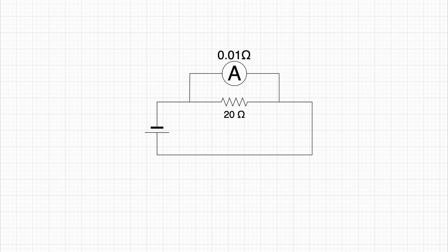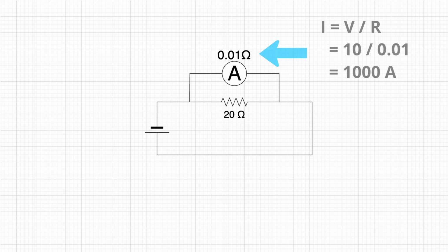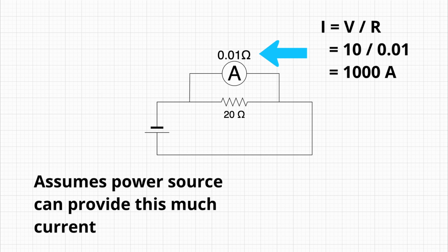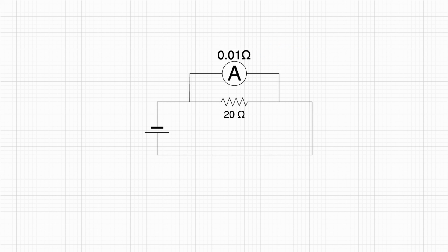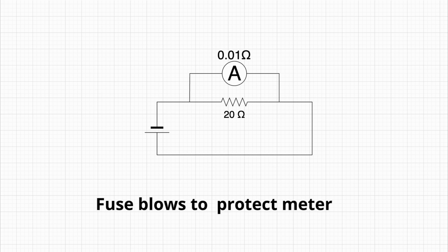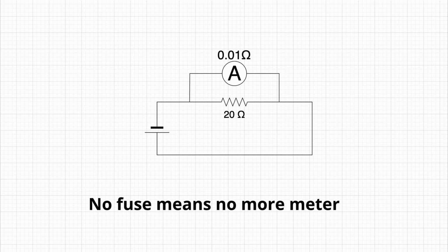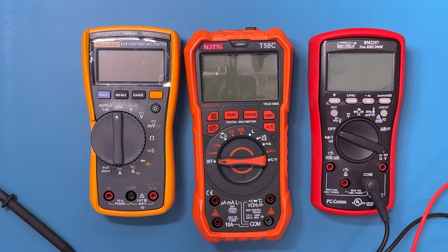Now, when we attempt to measure voltage using the current measurement pathway in the multimeter, we are placing the shunt resistor in parallel to the circuit we are measuring. Because the shunt resistor has a very low resistance, close to that of a pure short circuit, almost all the current that can be provided by the circuit at that point will flow through the shunt. As you know, a short circuit causes the opportunity for a very high amount of current. In a meter with a fuse, the fuse will blow, thereby protecting the internal circuitry of the meter. If no fuse is present, the circuitry will be destroyed. The best choice is to prevent this situation from occurring in the first place. Different meters have taken different approaches to prevent this from happening. Some show a message on the display when you are changing modes to remind you to move the test leads.